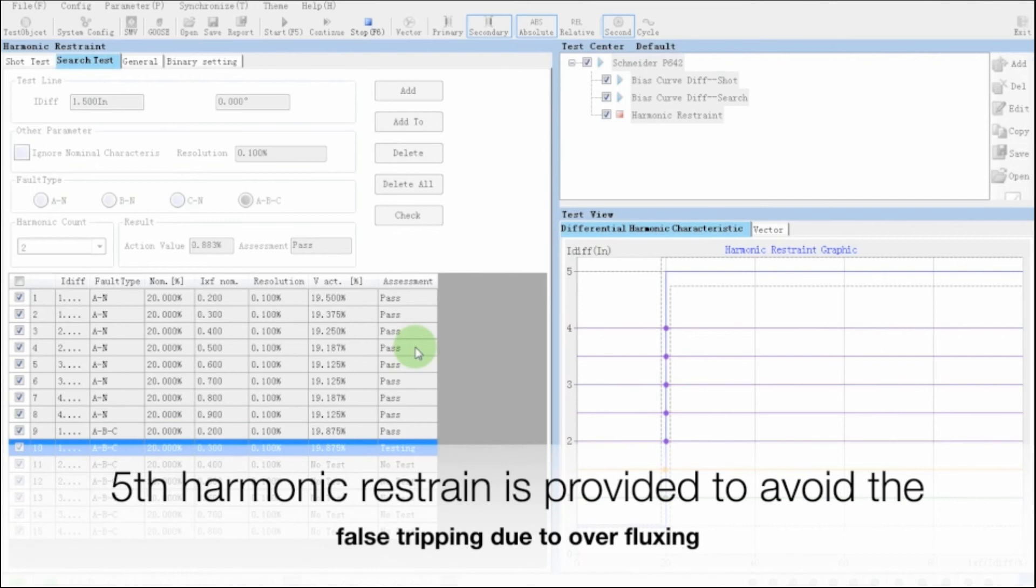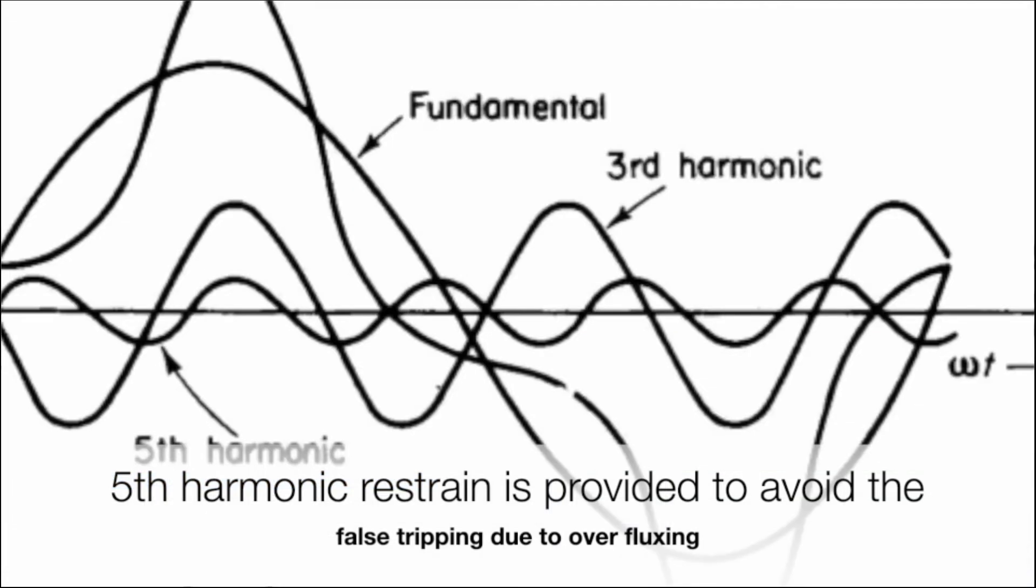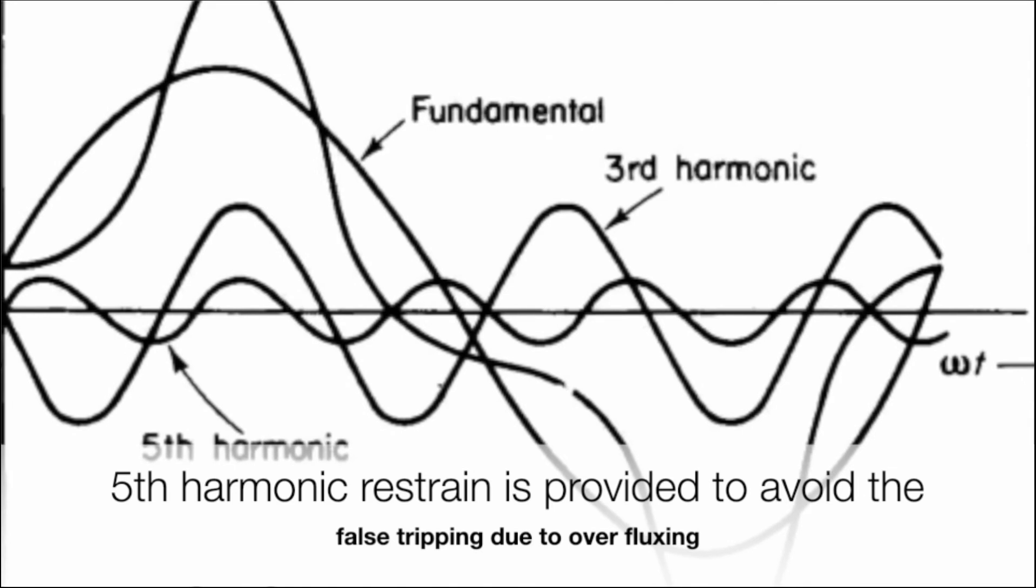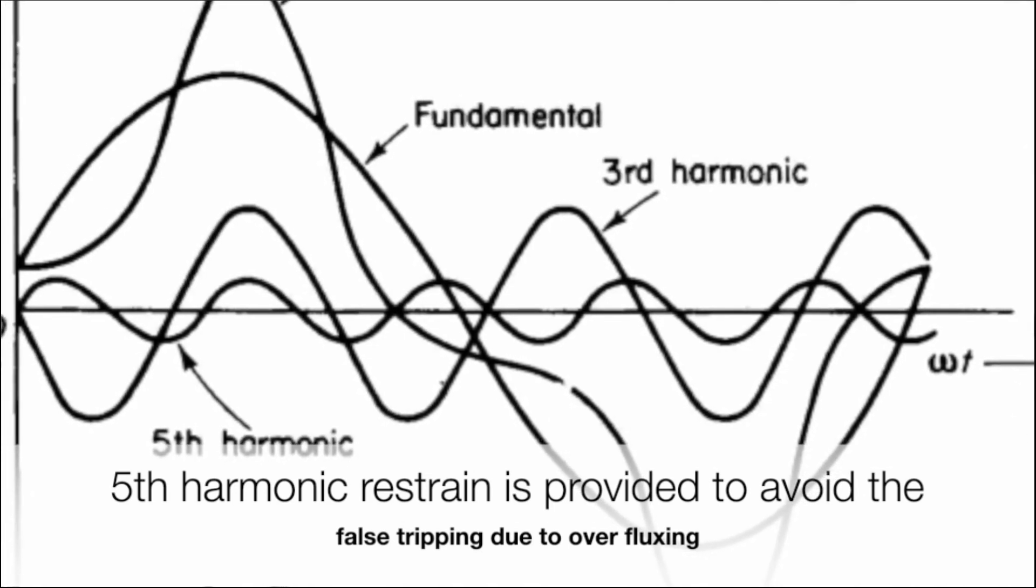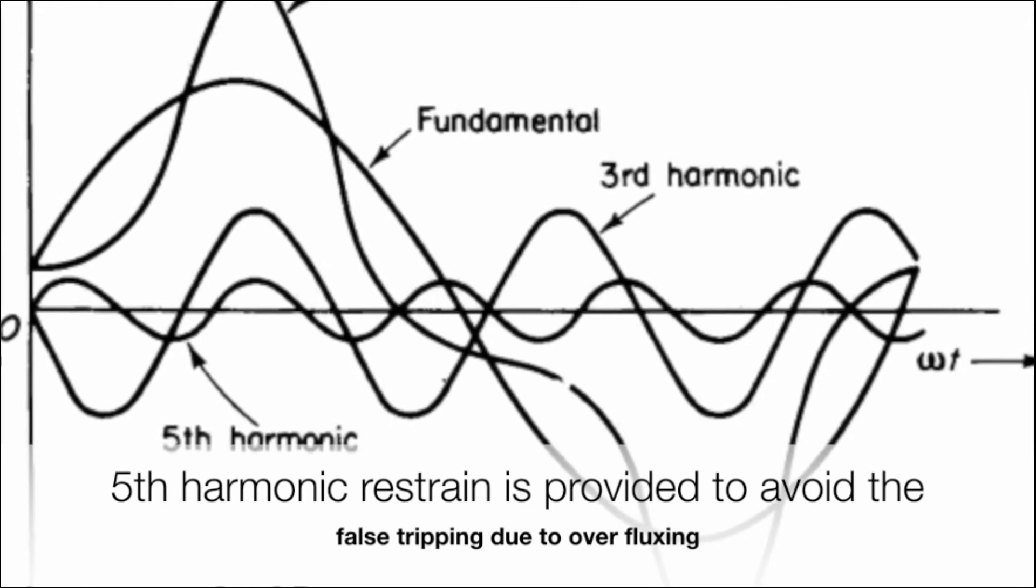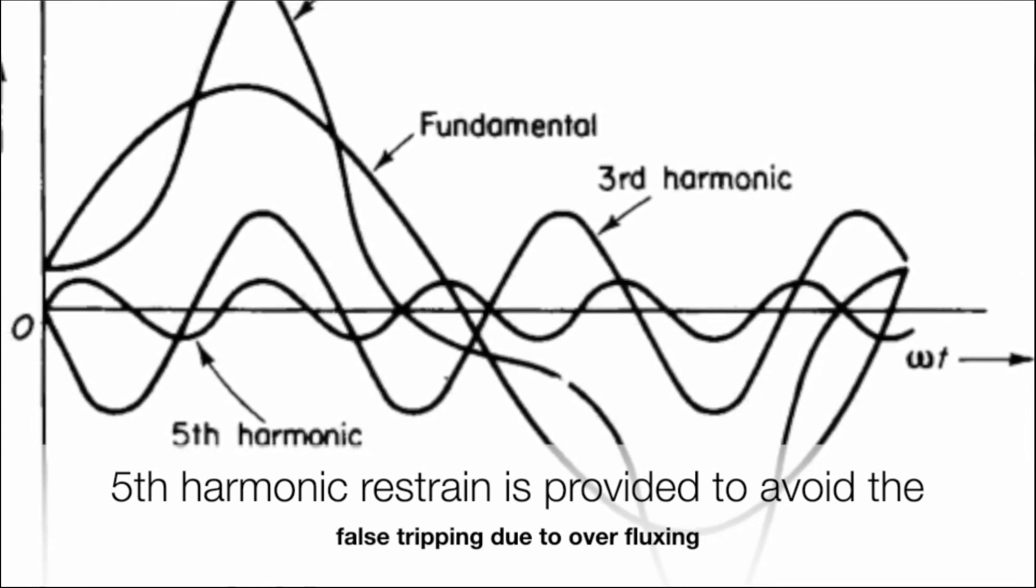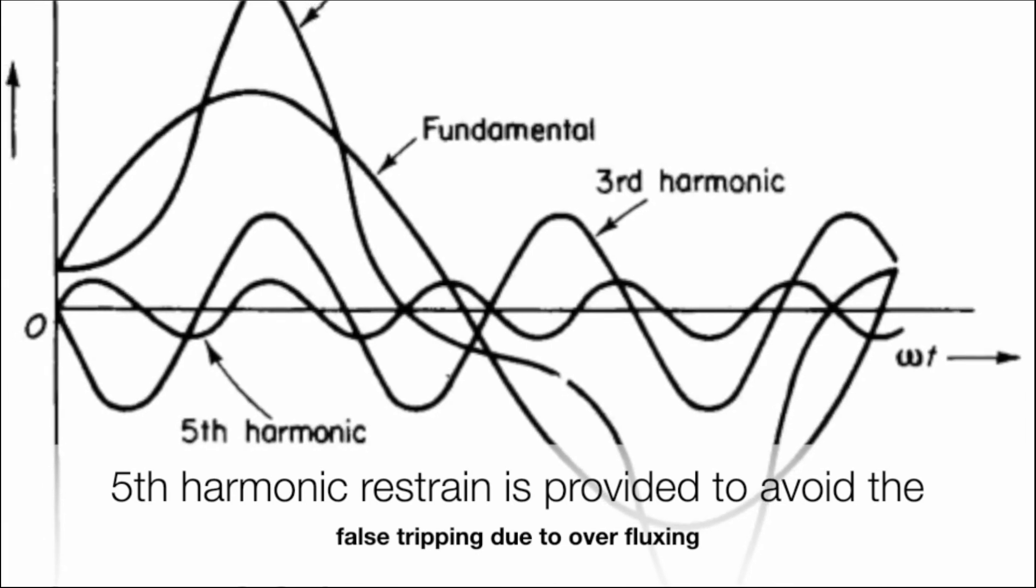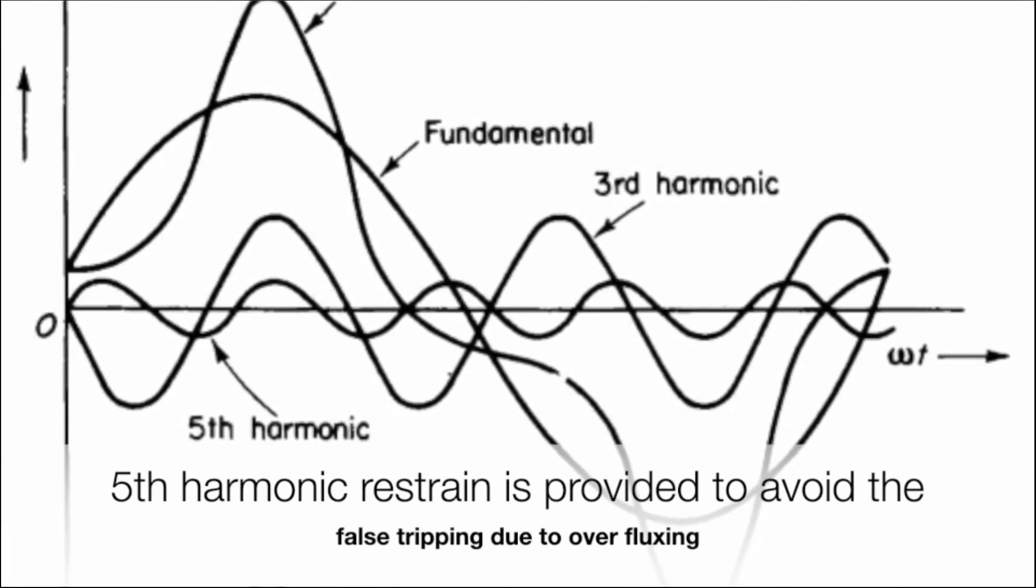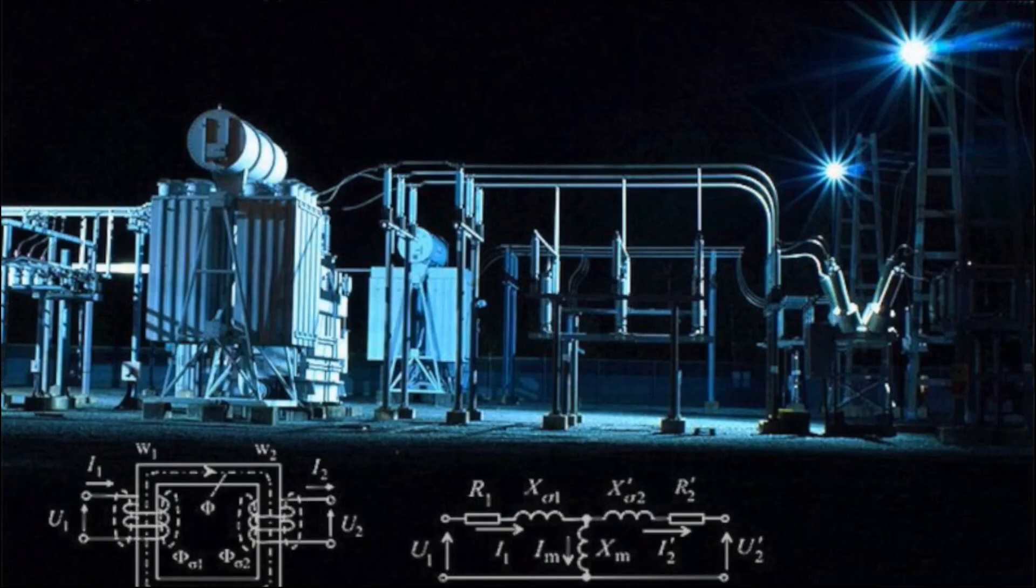Similarly, due to over-fluxing of transformer, the transformer current which is rich in fifth harmonic current may happen, so that the transformer is over-fluxed for some short time period around two seconds. So for this short period of over-fluxing should not cause the tripping of relay. Please note that during over-fluxing, the differential current Id will increase, which will operate differential relay.